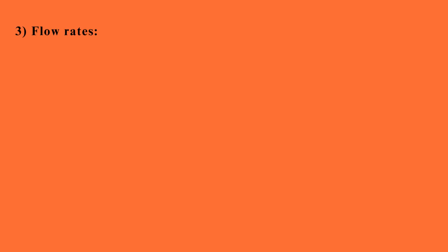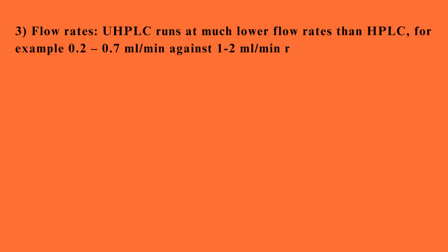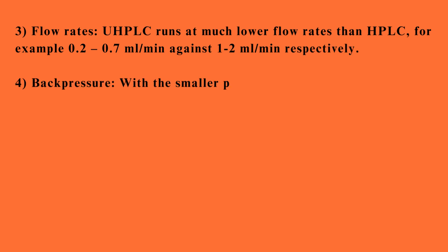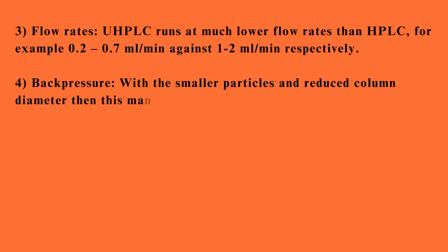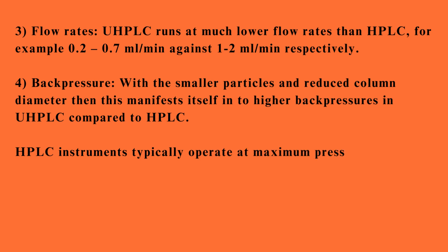Flow rates. UHPLC runs at much lower flow rates than HPLC, for example 0.2 to 0.7 ml/min against 1 to 2 ml/min respectively. Back pressure. With the smaller particles and reduced column diameter, this manifests itself into higher back pressures in UHPLC compared to HPLC.